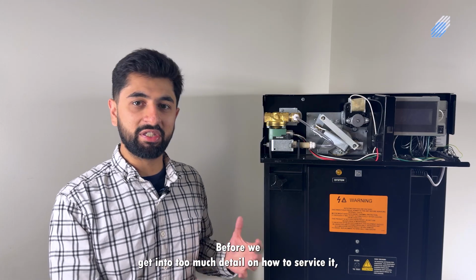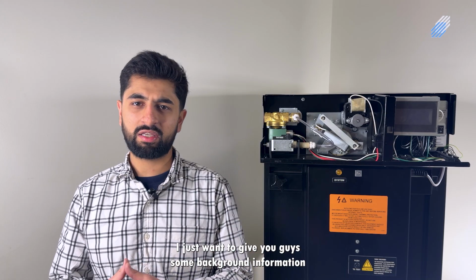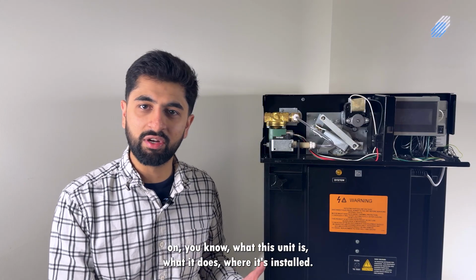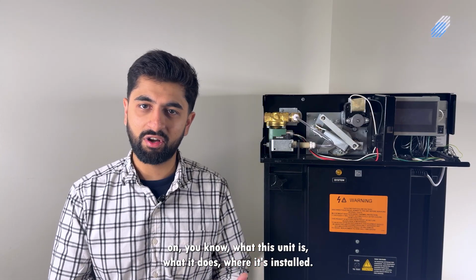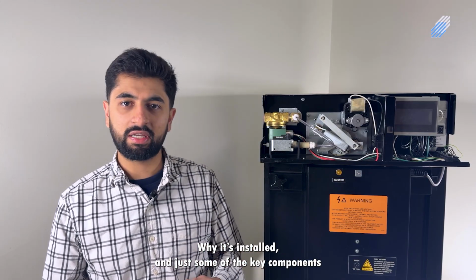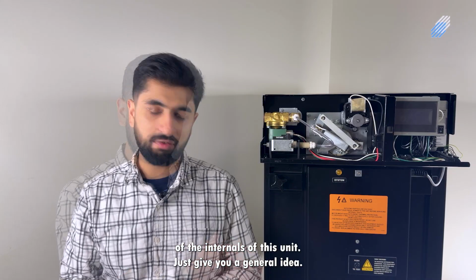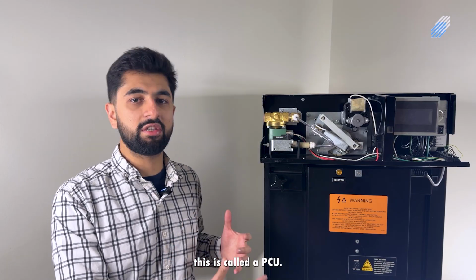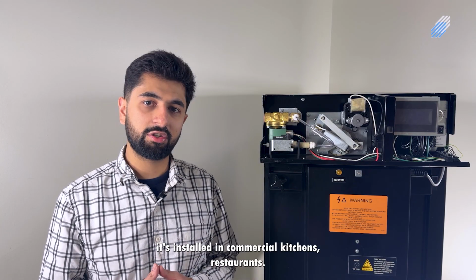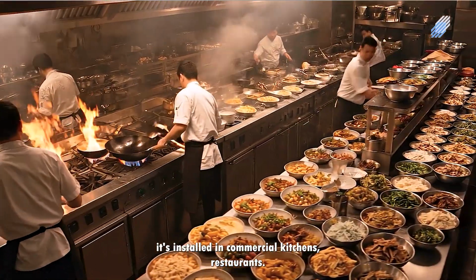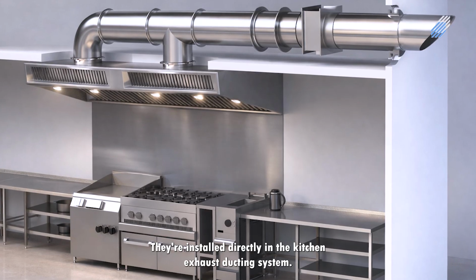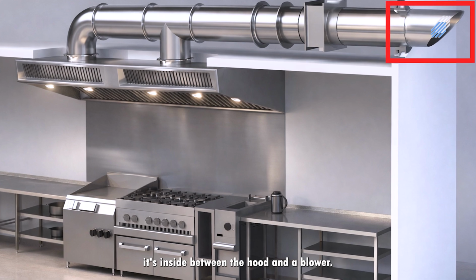Before we get into too much detail on how to service it, I want to give you some background information on what this unit is, what it does, where it's installed, why it's installed, and some of the key components of the internals of this unit. Just to give you a general idea. This is called a PCU. It's a pollution control unit. It's installed in commercial kitchens, restaurants. They're installed directly in the kitchen exhaust ducting system, between the hood and a blower.